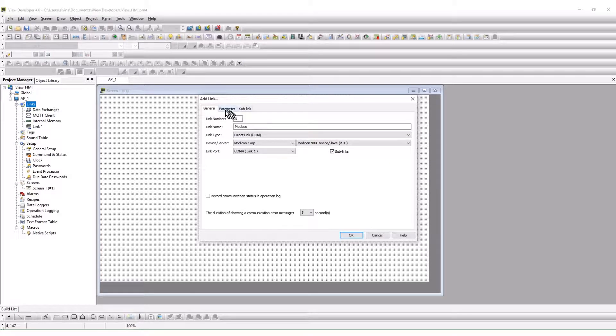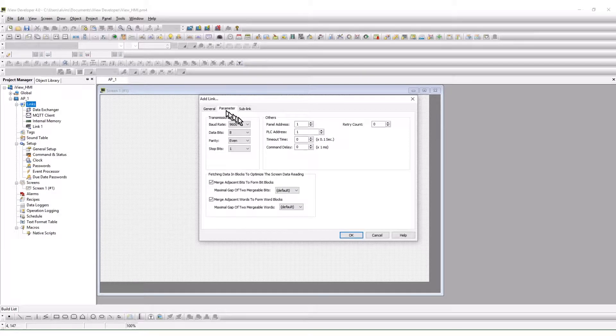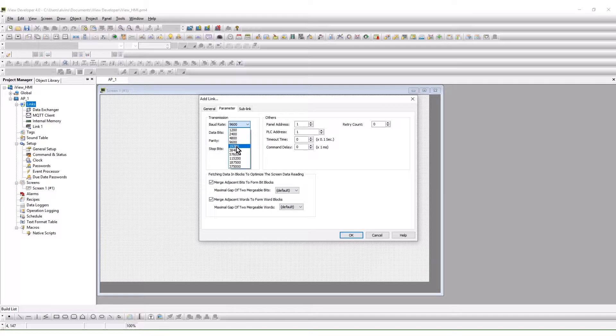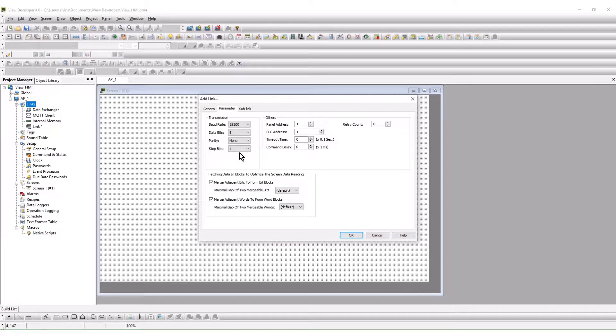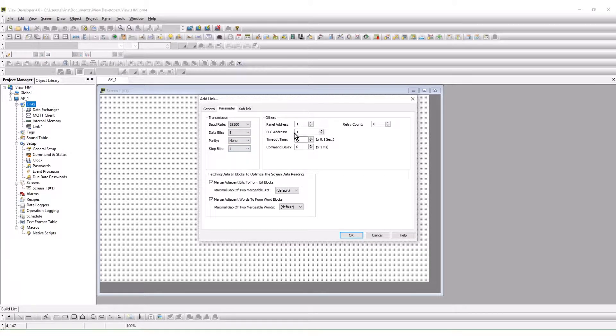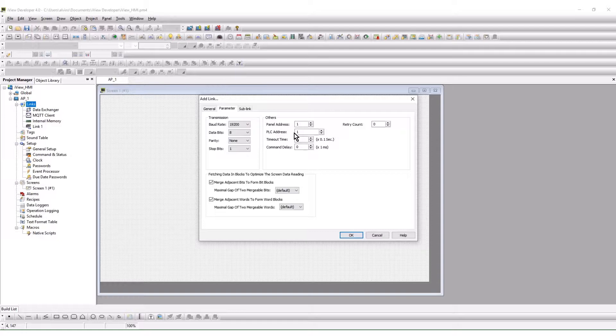From the parameter tab, the serial data parameters are selected. In this case, 19-2, 8, none, and 1. The PLC address is shown. This is the node or station address of the connected device. This is used when only one device is connected.